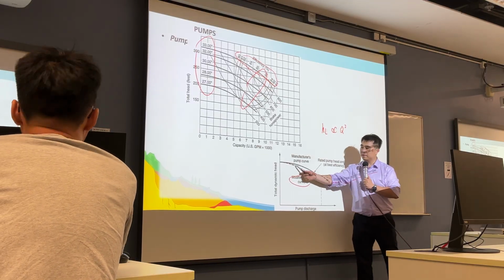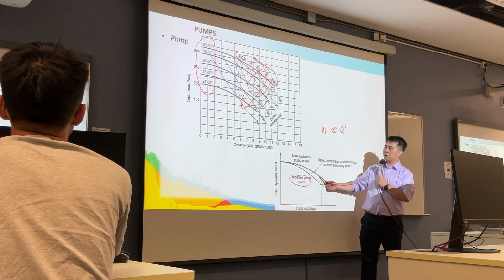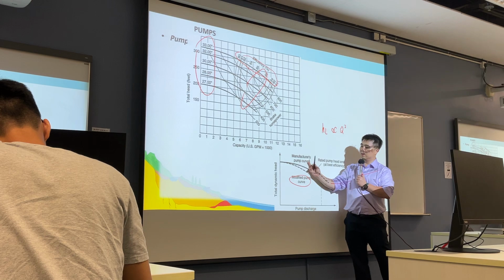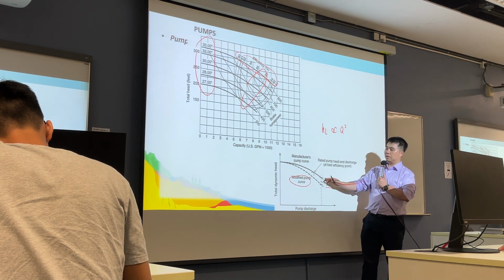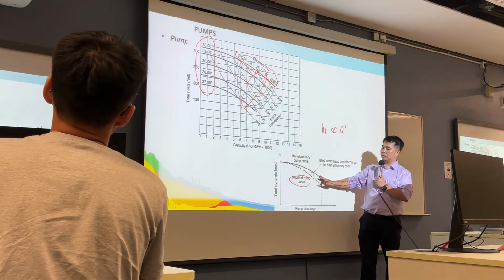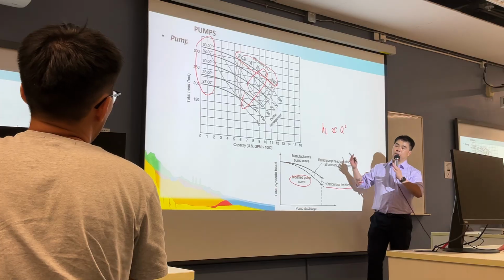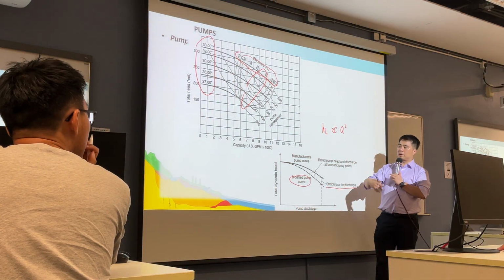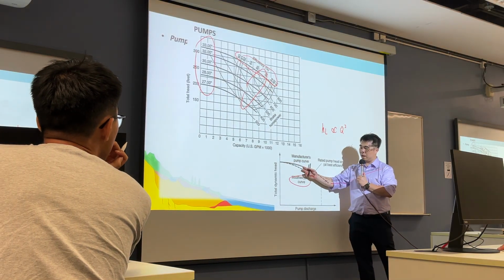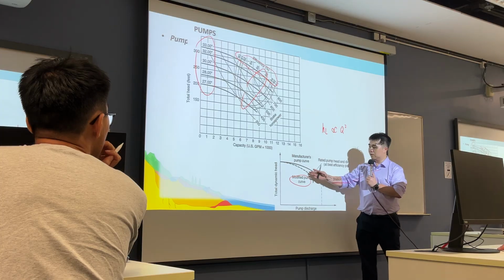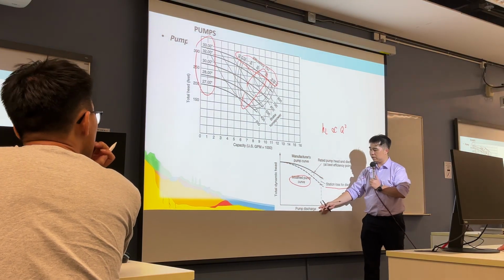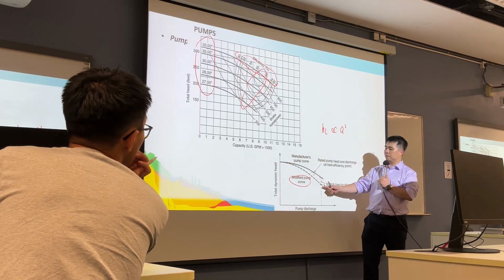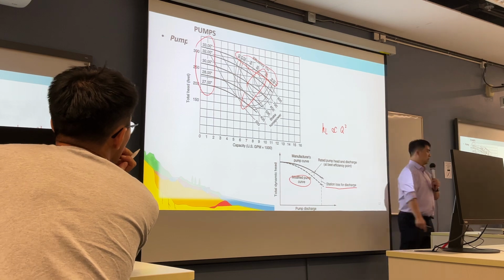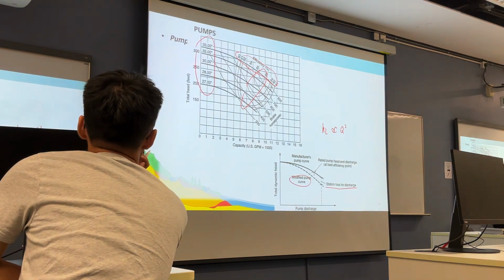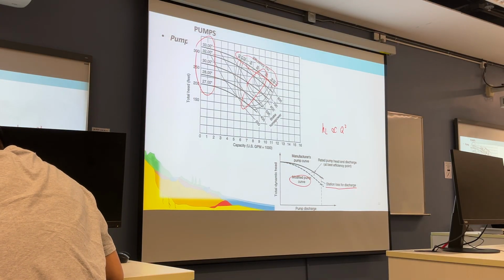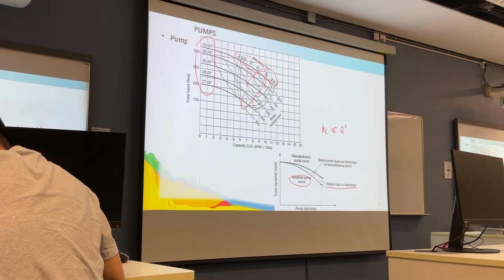So this solid line may be the pump curve from the manufacturer. You buy the pump and see the catalog. When the pump is brand new, it may produce performance like this solid line. But because you put the pump in a pumping station, you need to consider the head loss due to the piping and the entrance, and maybe other fittings, so there is a loss at different discharges. So you lower this performance to provide a modified pump curve. This depends on the pumping station piping setup itself, so the manufacturer cannot predict this for you.